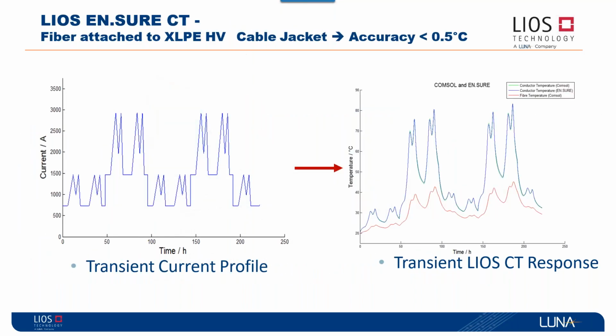From a quick illustration point of view, on the left graph you see technically how operators operate the circuits. They can go at 600 amps, then they keep going up and down based on the load and the demand, with peak hours between 8 a.m. and 5 p.m. and coming down also. These transients happening on a daily basis, especially for distribution networks, correspond to what we see on the right. In red is the fiber temperature responding to the current or the load on the line of the circuit.